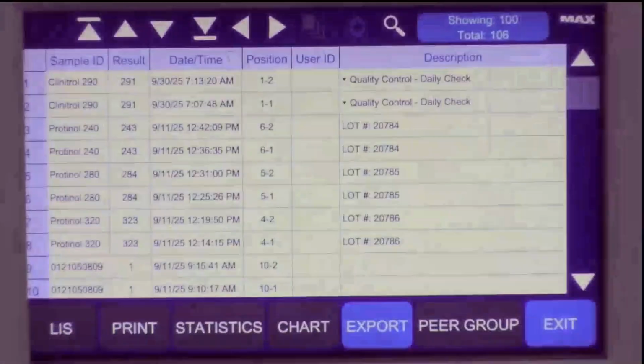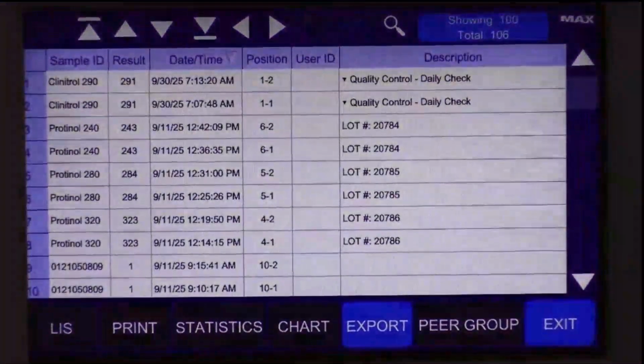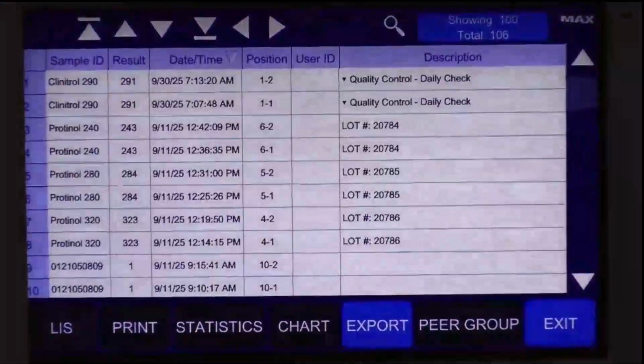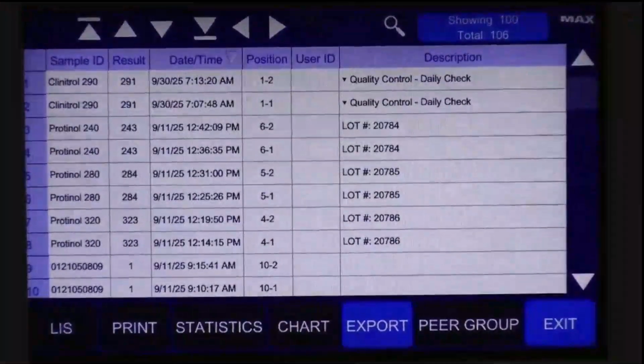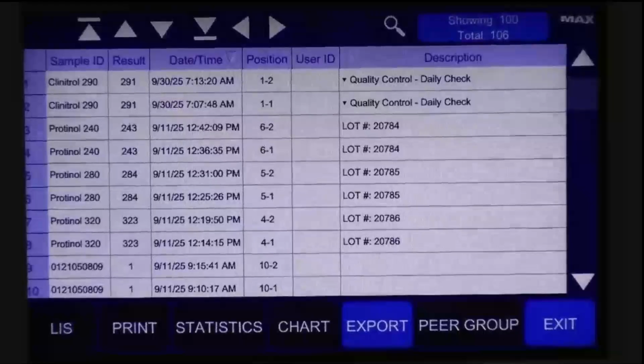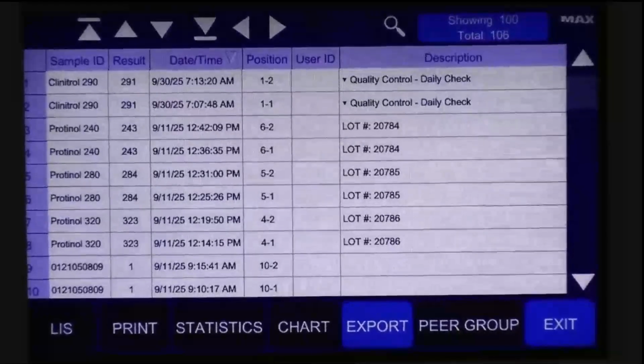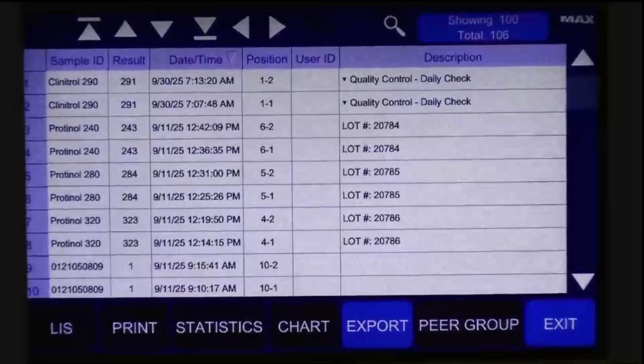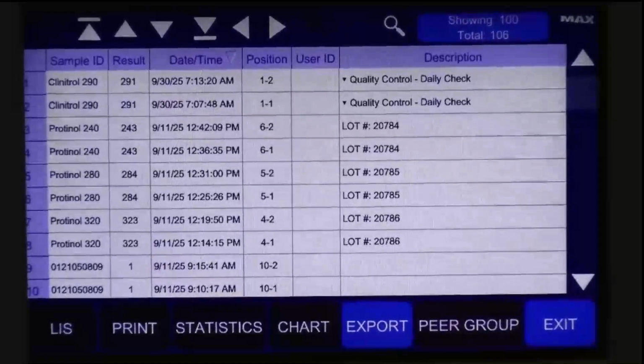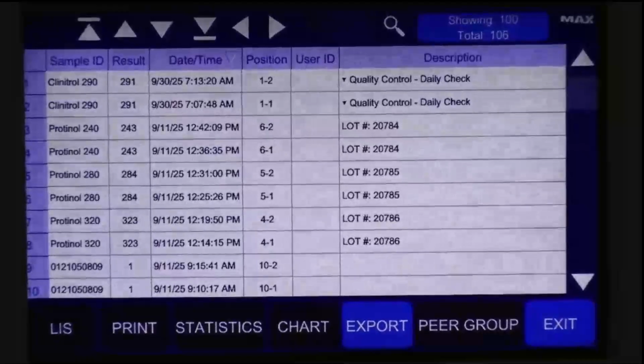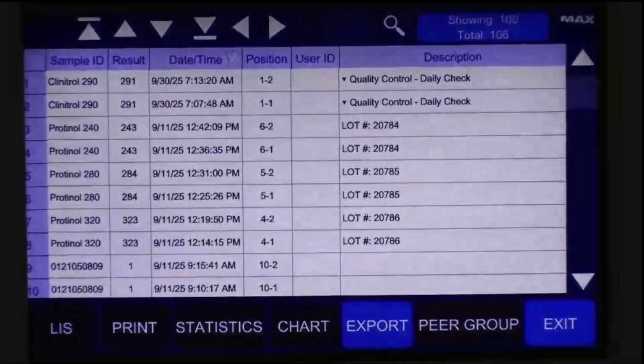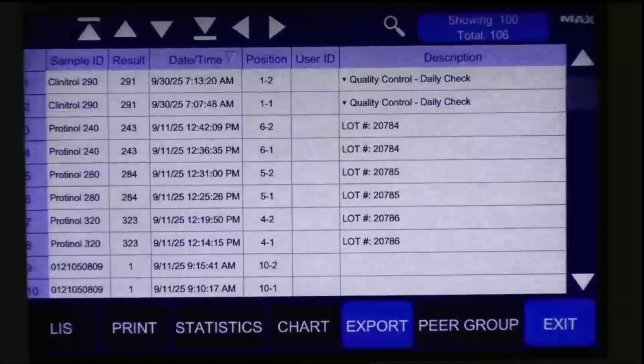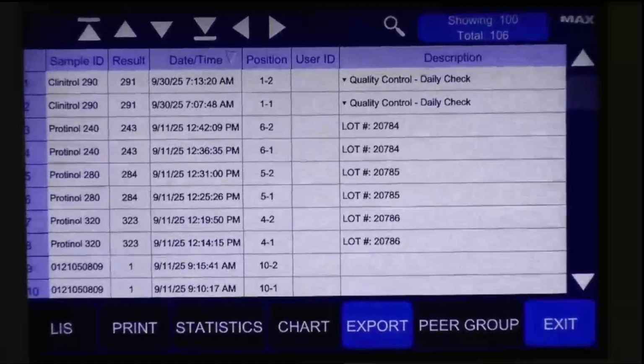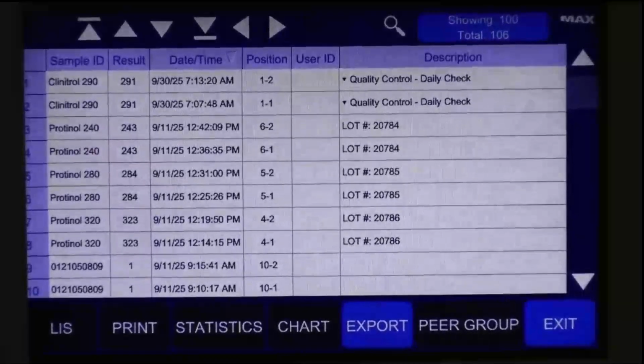What's great about this instrument is that it stores up to 1,000 results and 10,000 events. So in this result log, you'll store up to 1,000 results before anything rolls over and off of the instrument. Here you're going to see this LIS button. If I wanted to, I could select some results and try to push them through to the LAS. You're also going to see the print option. So if you purchase a printer separately, because there is no built-in printer on this instrument, you can connect that to the instrument and you can print out any results or statistics for a number of results.